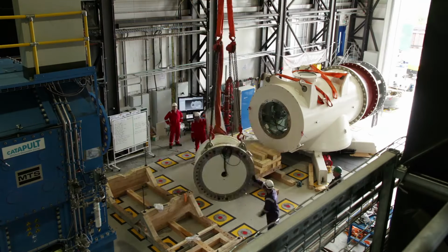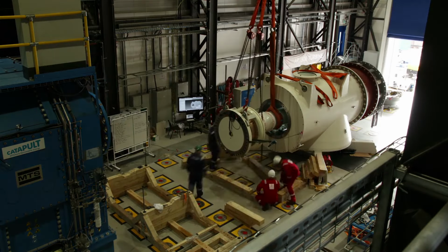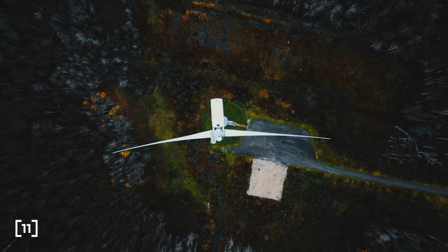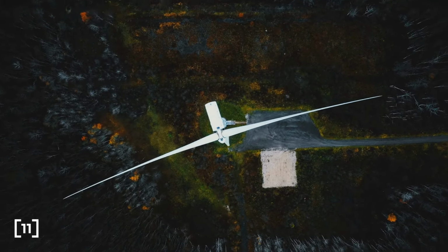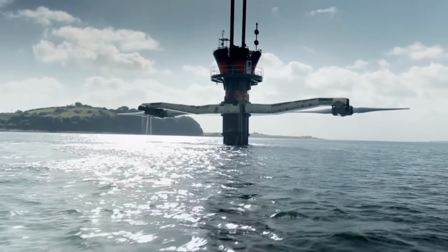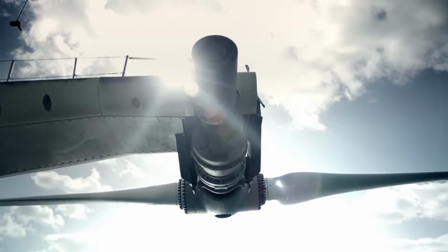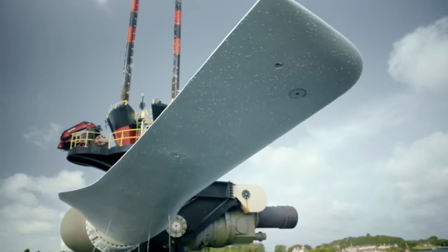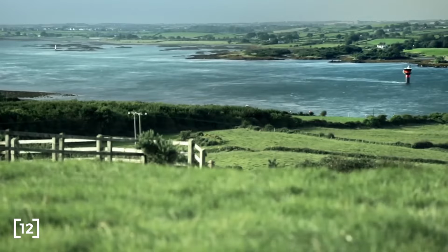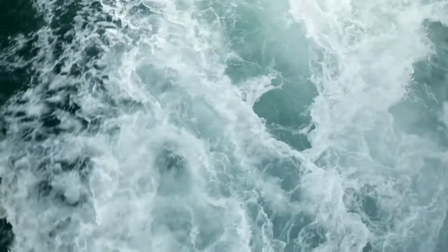That percentage is called a capacity factor, and 15% is a very low capacity factor, with Ireland's 5-year average wind energy capacity factor standing around 28%. However, this was a prototype, which did not run continuously and was routinely taken offline for inspection and research.